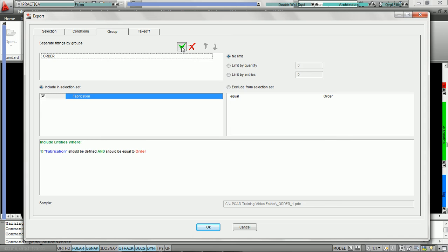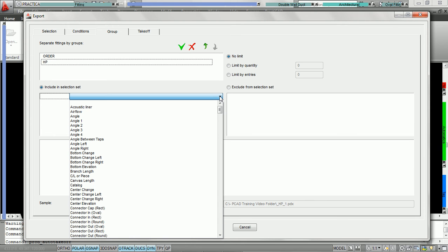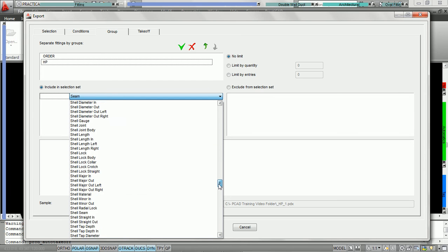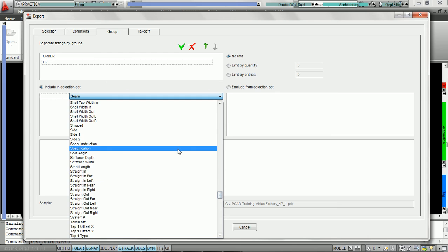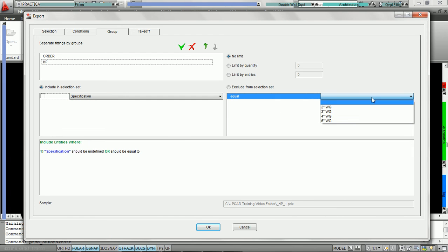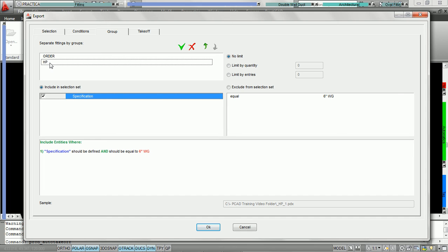Next, we're going to hit add again and add a second group. We're going to call it high pressure — we'll call it HP. Here, we're going to say if duct, and we're going to hit the letter S for specification. It's going to bring us to our S parameters. We're going to say if specification equals 6 inch water gauge, we want it to go to the high pressure group. So we've chosen the condition: specification equals 6 inch water gauge.